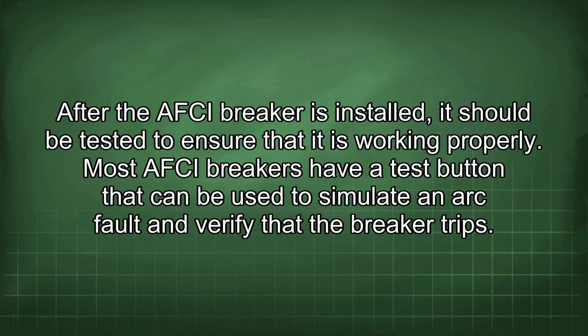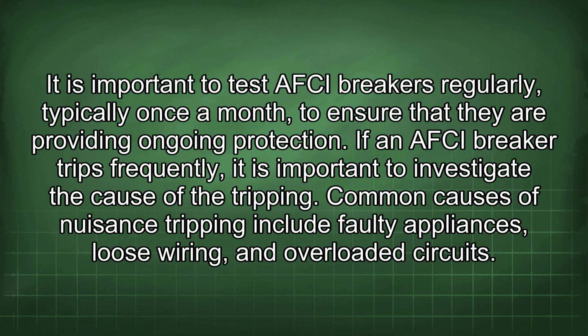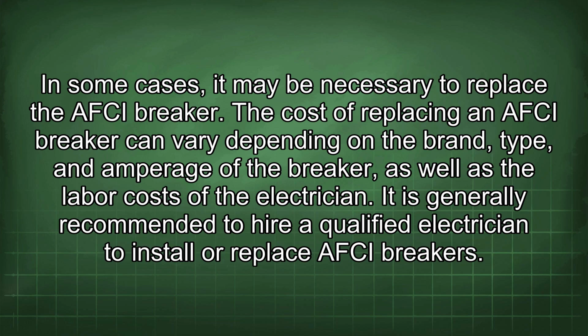Most AFCI breakers have a test button that can be used to simulate an arc fault and verify that the breaker trips. It is important to test AFCI breakers regularly, typically once a month, to ensure that they are providing ongoing protection. If an AFCI breaker trips frequently, it is important to investigate the cause of the tripping. Common causes of nuisance tripping include faulty appliances, loose wiring, and overloaded circuits. In some cases, it may be necessary to replace the AFCI breaker.